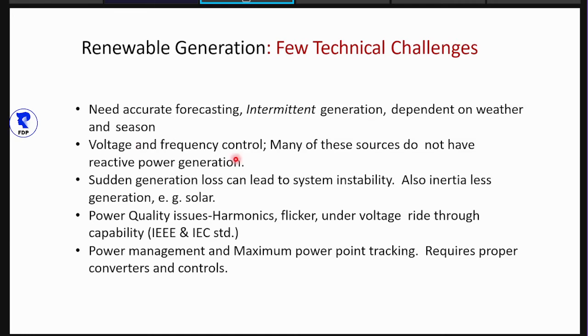So voltage and frequency control is an issue, as many of these sources do not have reactive power generation. As you know, solar power plant supplies only active power, so reactive power is not there. You have to install some capacitor to supply reactive power. So the combination of solar and capacitor can supply both active and reactive power.